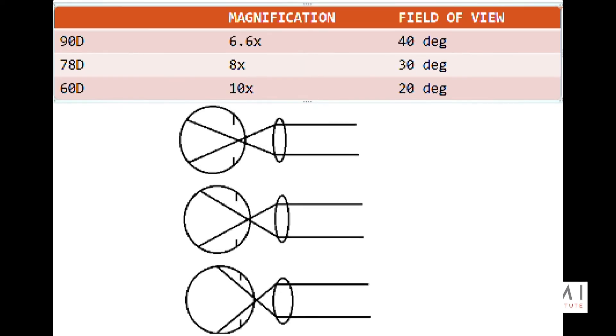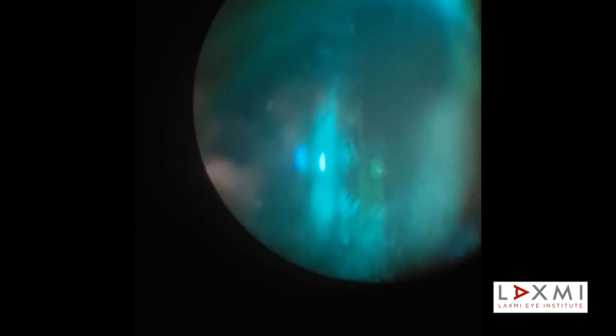For a 90 diopter lens, magnification is 6.6x with a 40-degree field of view, whereas for a 78 diopter lens, magnification is 8x with a 30-degree field of view. A red-free filter can be used for better contrast between retinal vessels and the underlying background, and also to detect early losses of nerve fiber layer for suspected glaucoma.